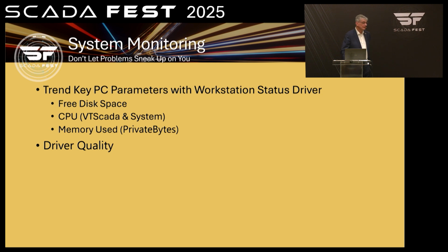Driver quality is another little hidden one. There's a value in the drivers that indicates essentially the percentage communication quality. So 100% means no issues. Every packet going out is coming back. If you're working on a less reliable channel, typically like a VHF radio, fewer of those nowadays, 95% is probably okay. That's typical. They fail a lot. Birds fly by, the wind blows, a car drives by.